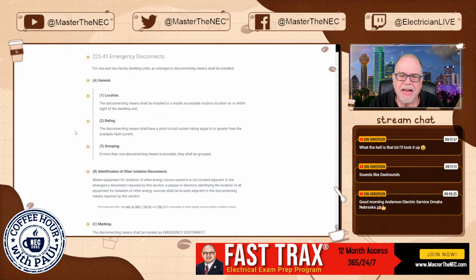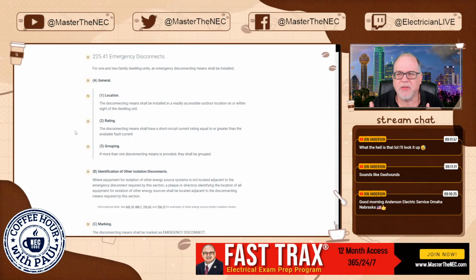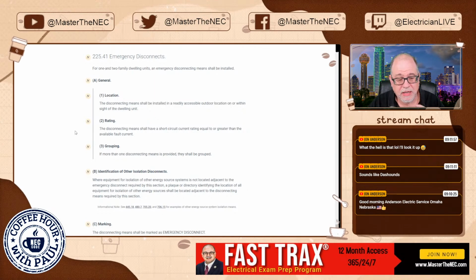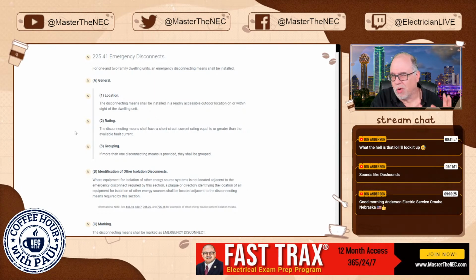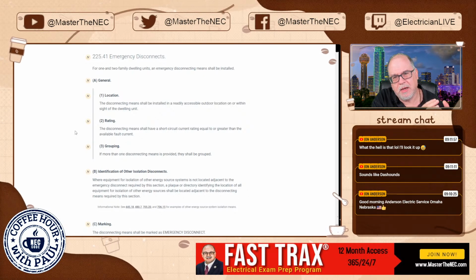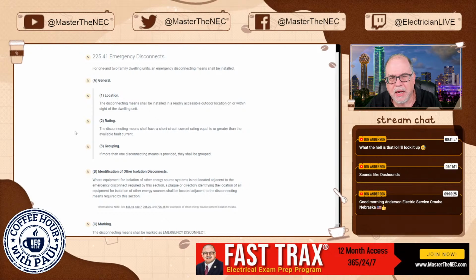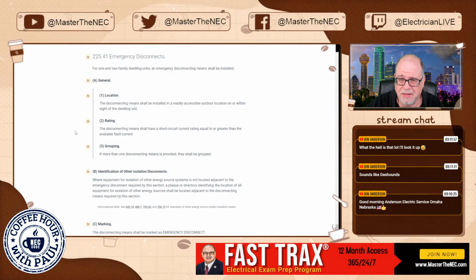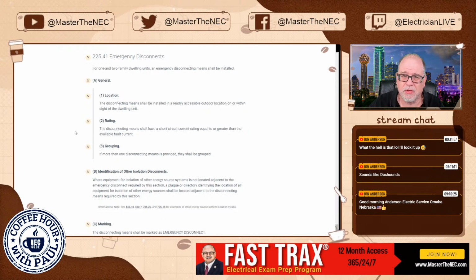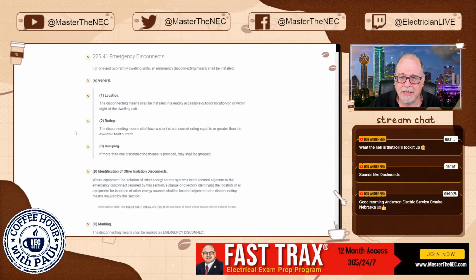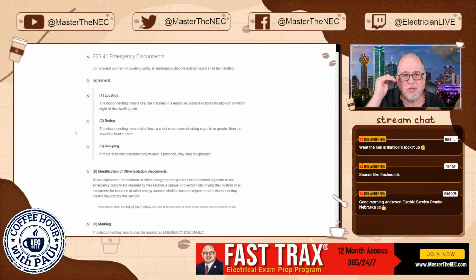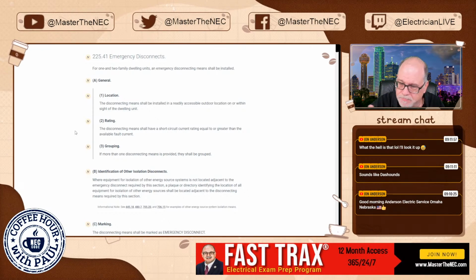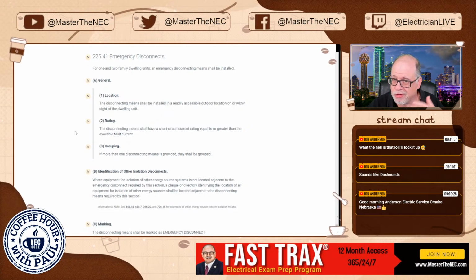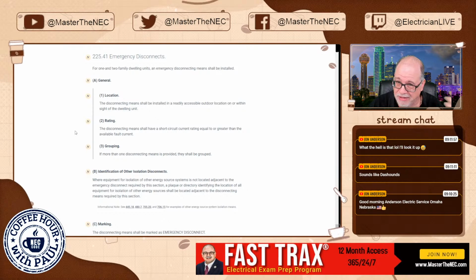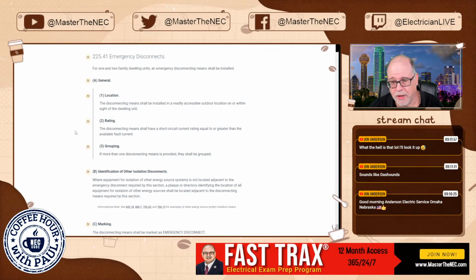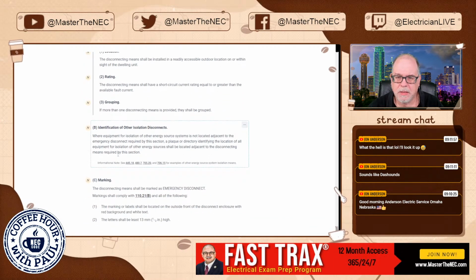Now, the rationale behind this, again, is the same as it was for the services. You could have the service equipment on a pole, let's say, and you're running to this dwelling unit, and the first responders get there and they have no idea where the disconnect is to kill power to this 1 or 2 family dwelling, right? So you need to be able to provide it there so they don't have to go searching. They're going to go right there to it, okay? Now, some people agree with this, and then some people are still upset about the rule in 230.85. But again, it's not going anywhere, so might as well get used to it.